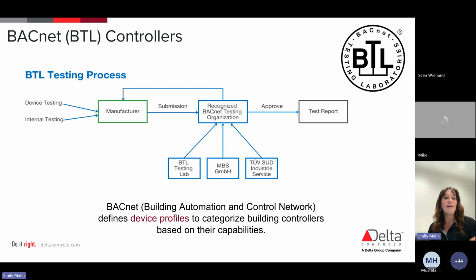You can see there on the left where we see device testing and internal testing. That's done by the manufacturers. So manufacturers, all of us, are going through and doing all of this pre-testing using all of the BTL resources, and then we submit it to a recognized BACnet testing organization. They're recognized, but they're third party. Then they take it through a bunch of different tests.